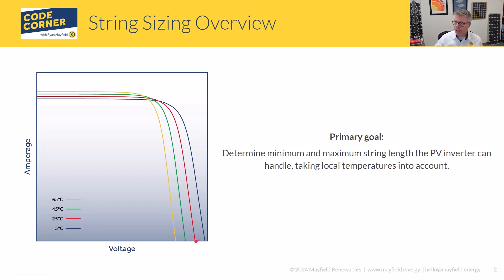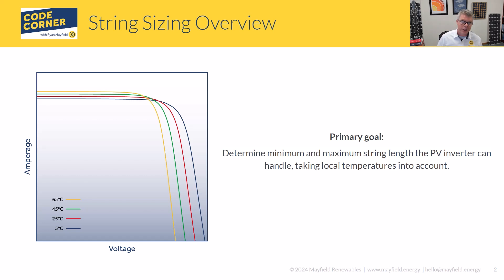I'll highlight this with my laser pointer here. This red line — this point here — is the 25 degrees C line, which represents the standard test conditions. You can see this IV curve as it goes up and crosses over. What we're focused on is what it does down at the voltage. The PV modules have an inverse relationship with voltage, meaning that as they get colder the voltage increases, and as they get hotter the voltage decreases. If we go over to the left one from that red line, we have the 45 degrees C point. At 45 degrees C, you see that the open circuit voltage and the max power voltage — represented at the knee of the curve — both decrease relative to 25 degrees C. If you get even hotter at 65 degrees C, you see you drop even more.